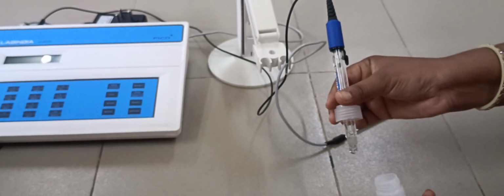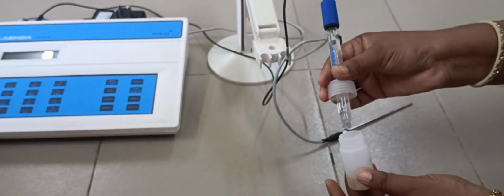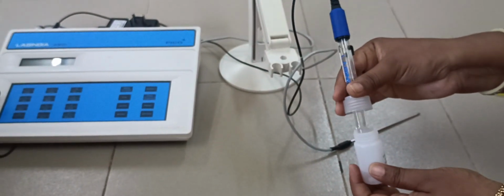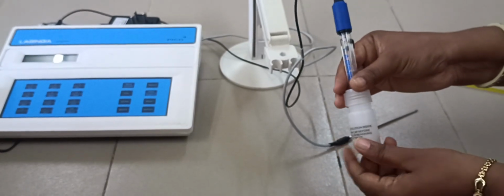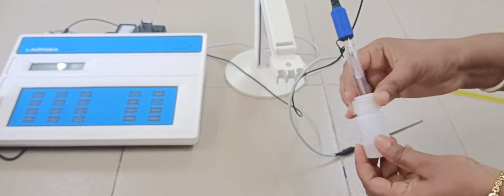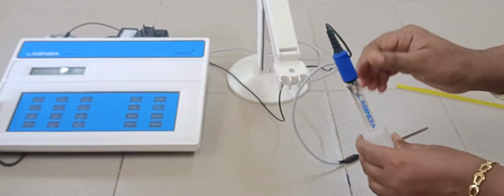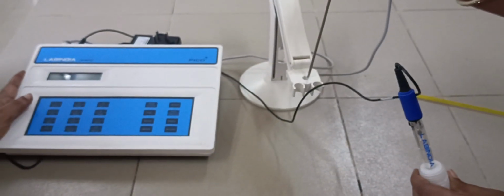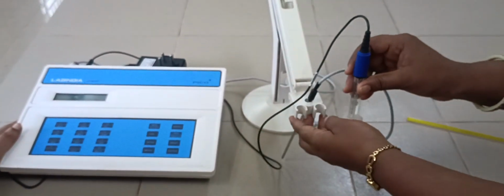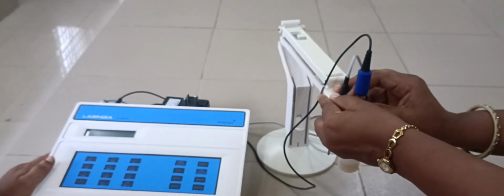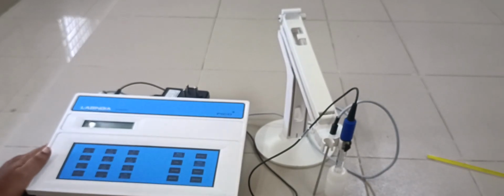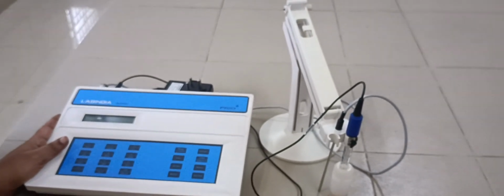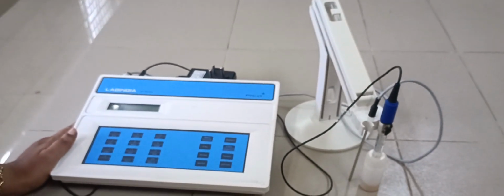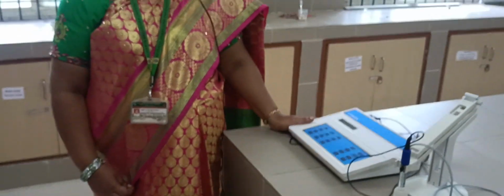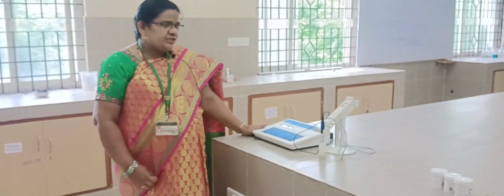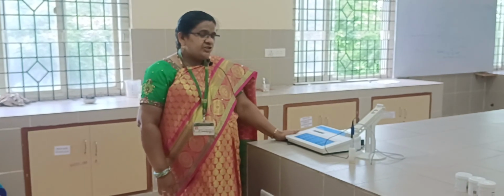What is the principle here? When we dip this glass bulb into the solution, the hydrogen ions from the solution enter through the glass bulb. The glass bulb already contains metal salts, and the metal salts are exchanged. Because of ion exchange, an electric flow is generated. The electric flow is captured by the silver wire, which generates the voltage. The generated voltage is compared with the reference voltage. The voltage produces electrical signals that give the pH of the solution. This is the working principle of the pH meter generally.